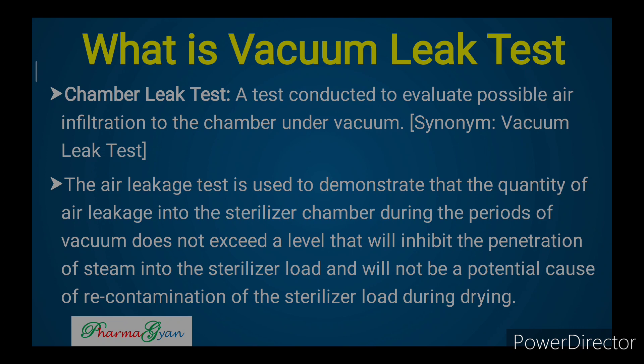The major reason for performing the vacuum leak test is that whenever we perform sterilization, air should not be present. If air is present, the sterilization will not be effective. Air bubbles and air pockets cause ineffective sterilization.